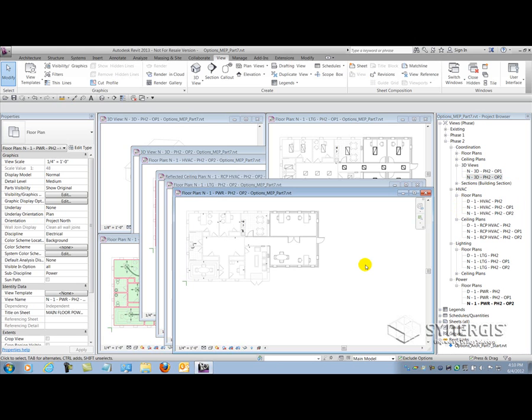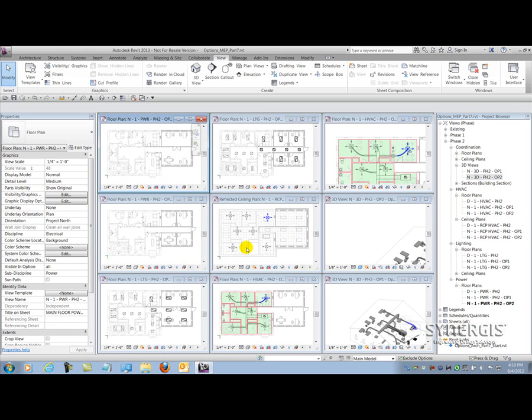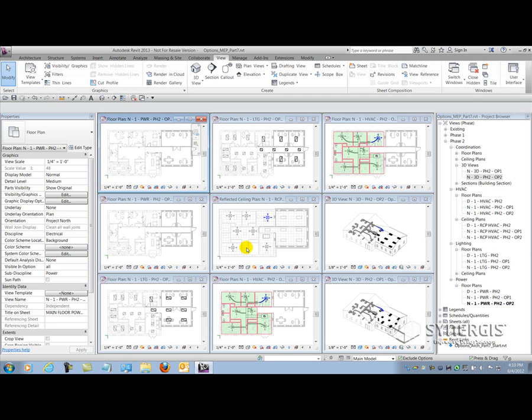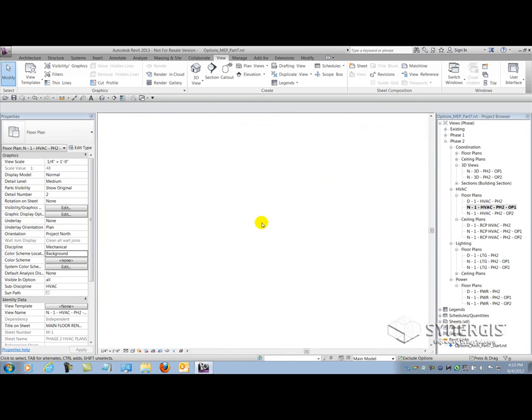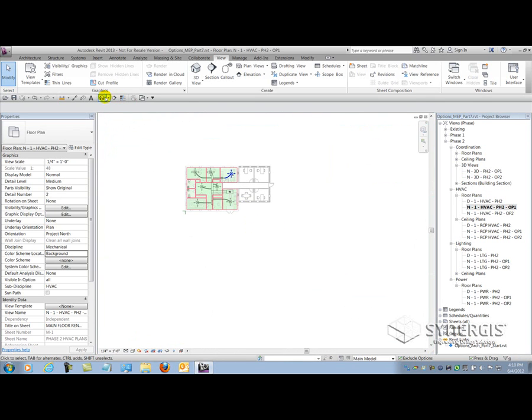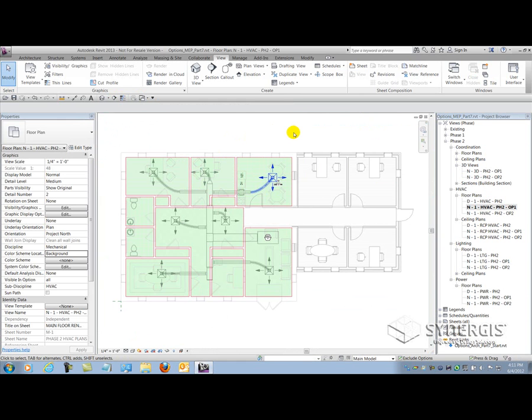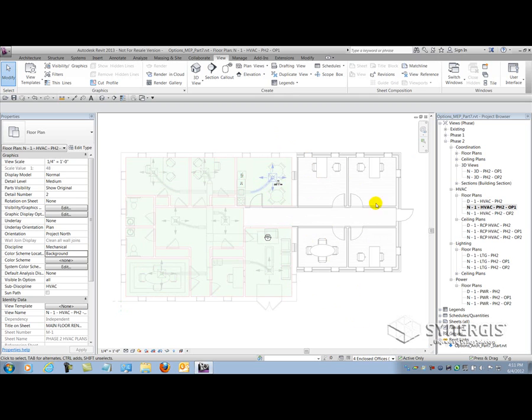Now that all the views are open of all the options, I want to start focusing on mechanical. One of the primary goals of the mechanical engineers is to explore the volumes of the building and figure out the peak heating and cooling loads that will have to happen on this building in order for me to size my system correctly and layout my system correctly. One of the things that you're going to find out is when you start getting into spaces and zones when design options are in place, you're going to run into a brick wall. I'm going to open up the HVAC plan for option one here. This is actually showing option one of the architects file and I need to go add spaces to option one. The first thing I'm going to do is set my active option to the four enclosed offices.